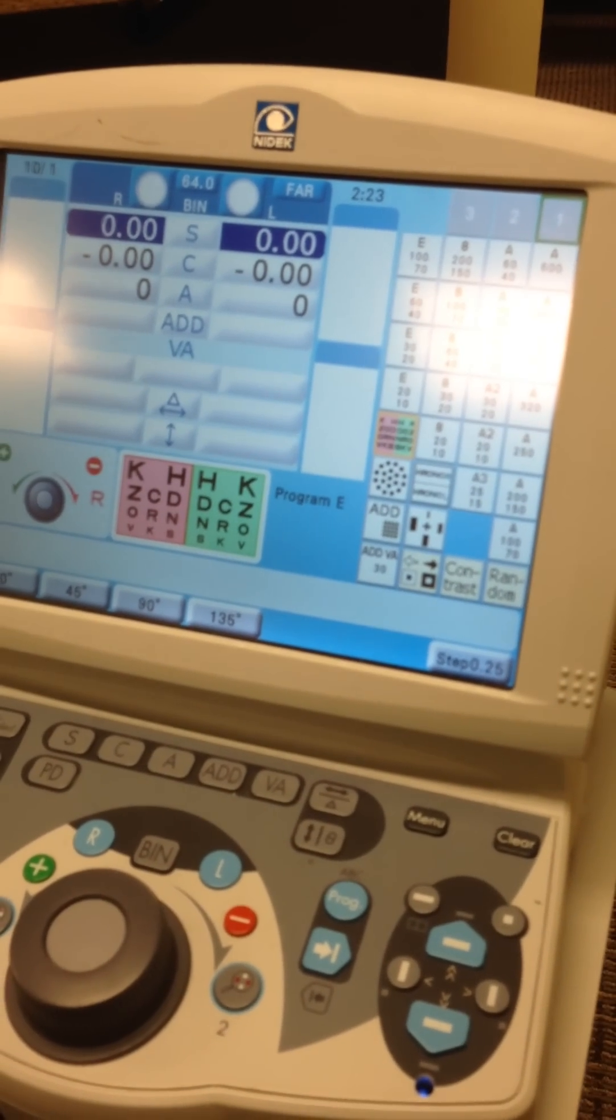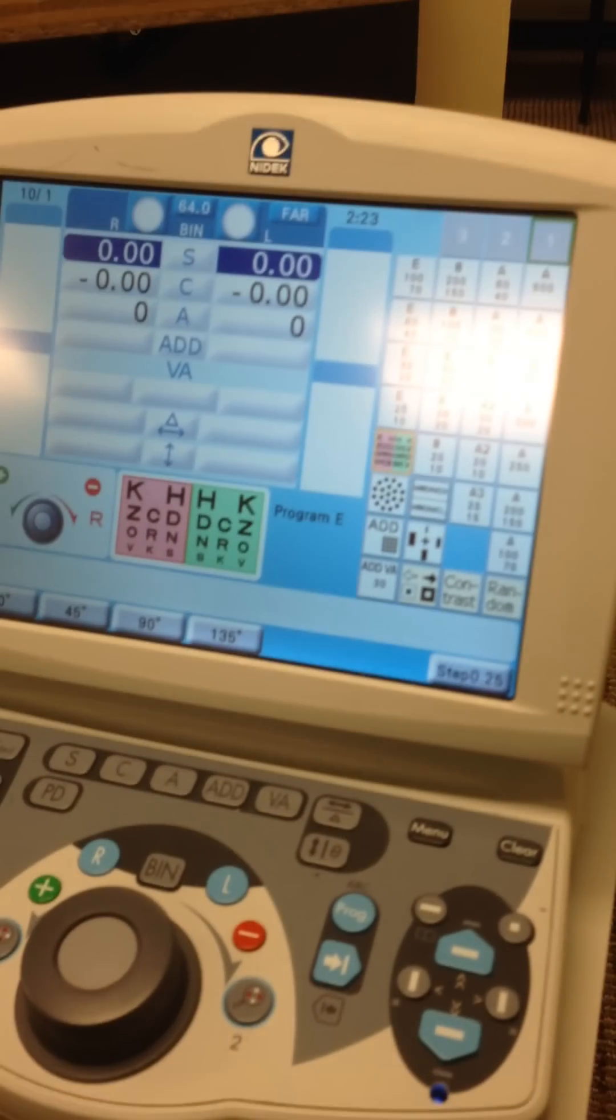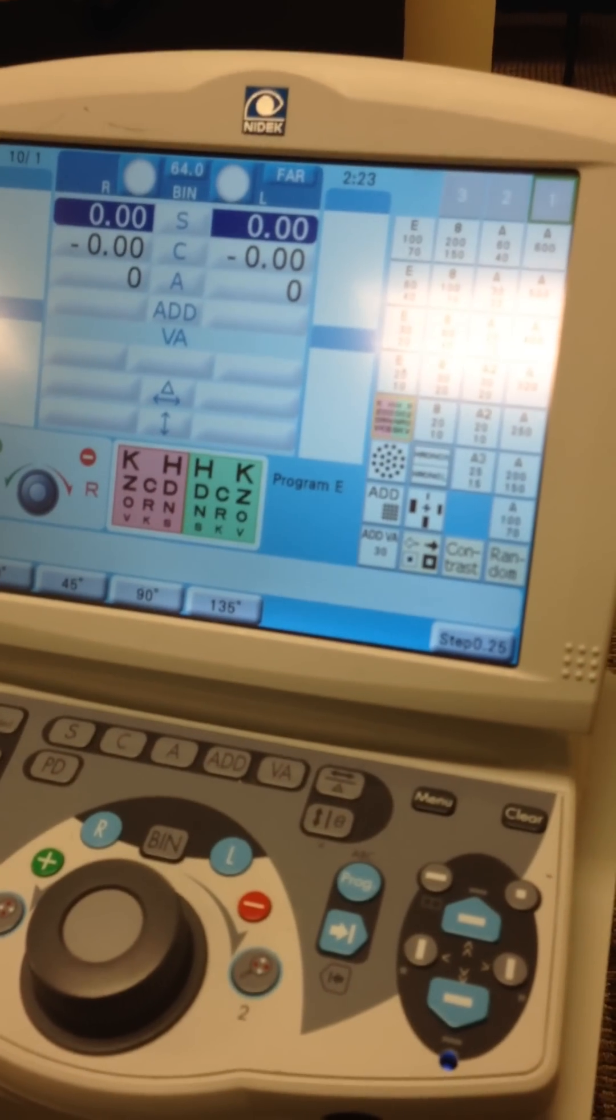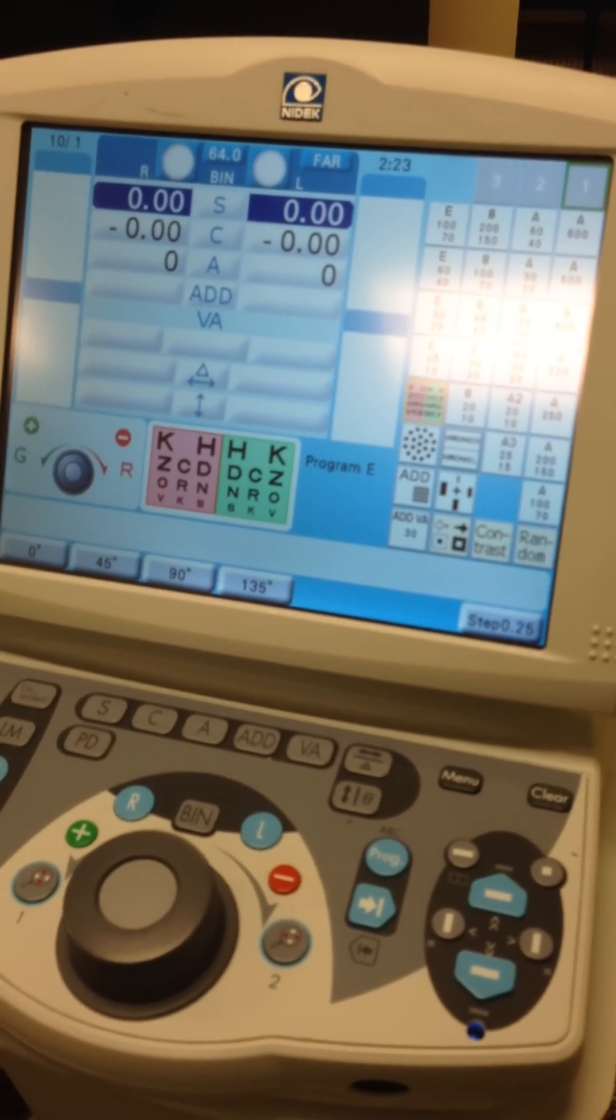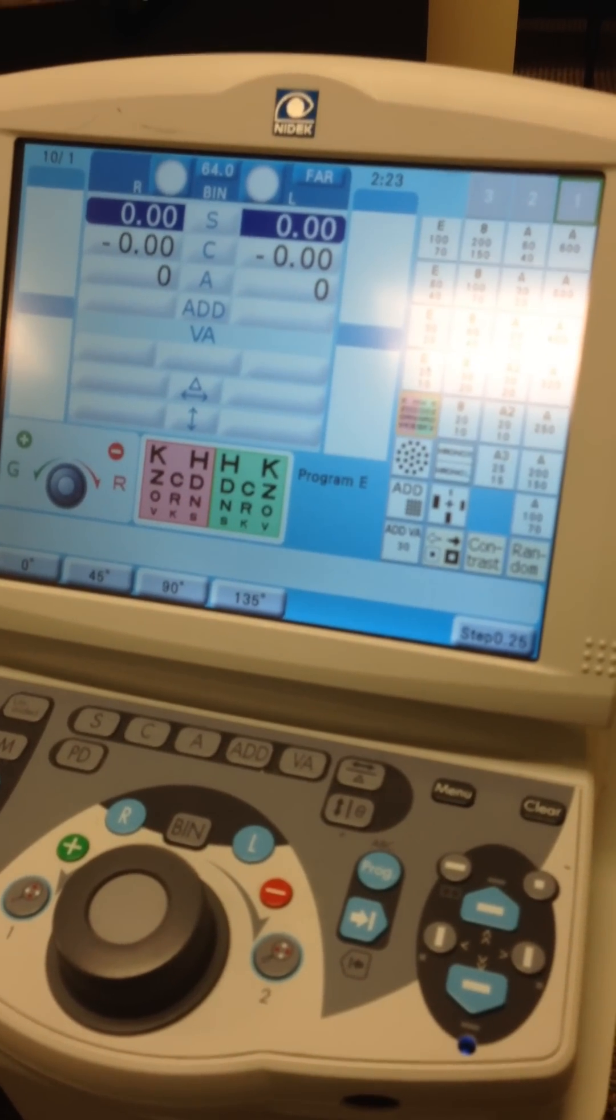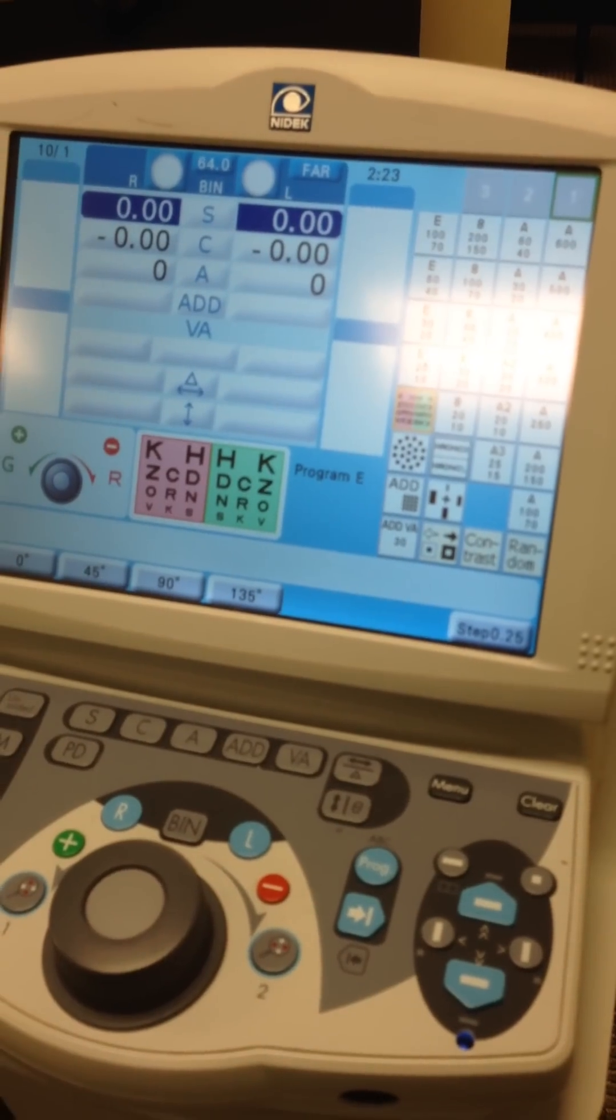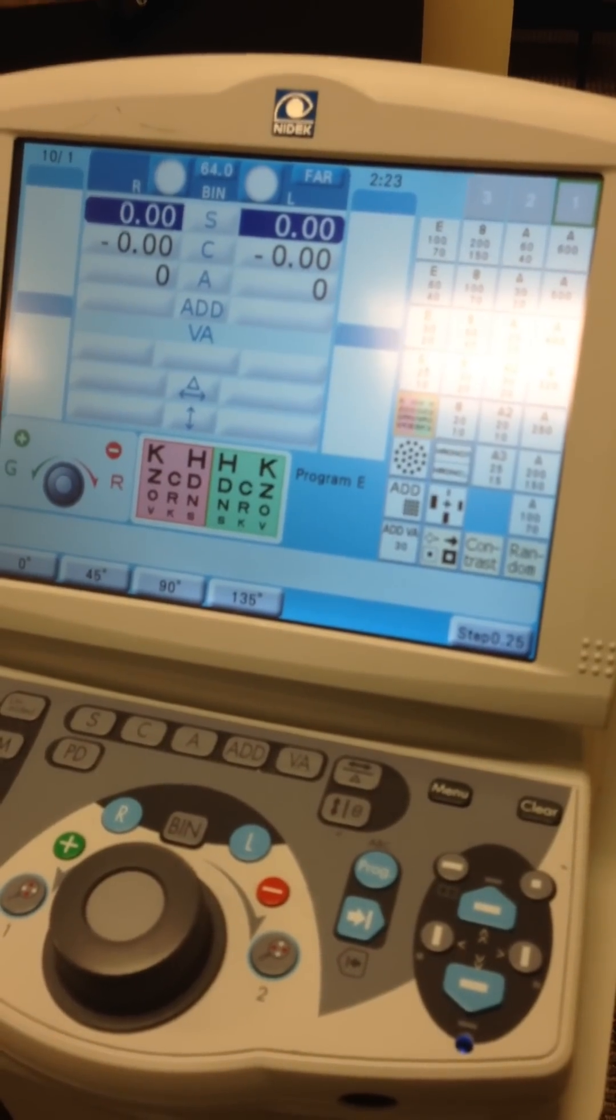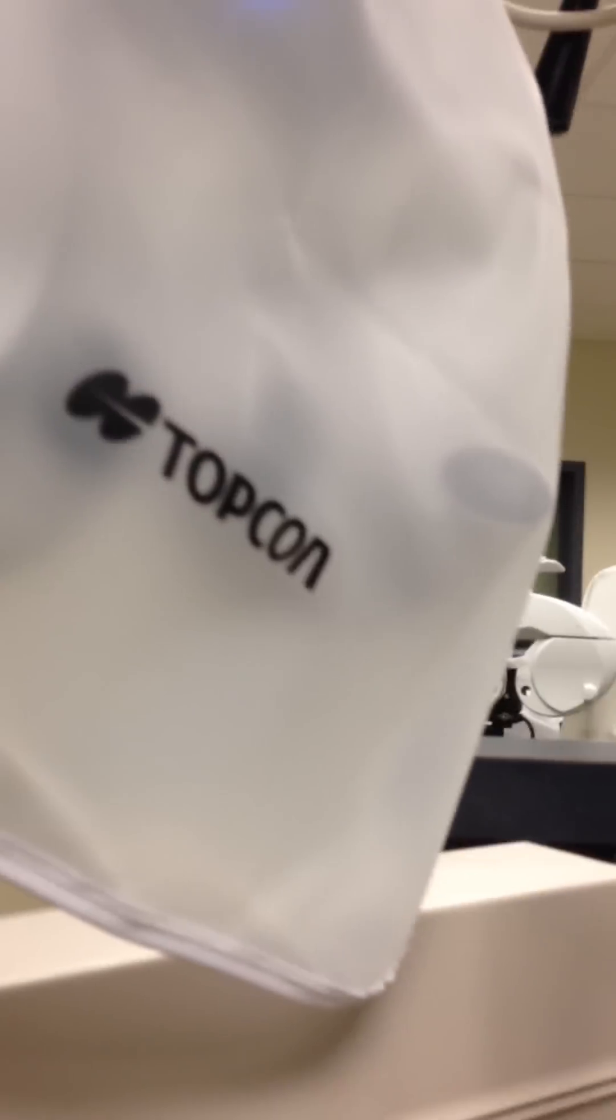I'm going to make a quick video from the procedures room showing you how to use the contrast and stereo, Lea stereo functions on the Marco automated phoropters. You can see here we have the chair and stand as you typically would in the procedures room. This one says TopCon on the holder, but it's really a Marco if you look careful.